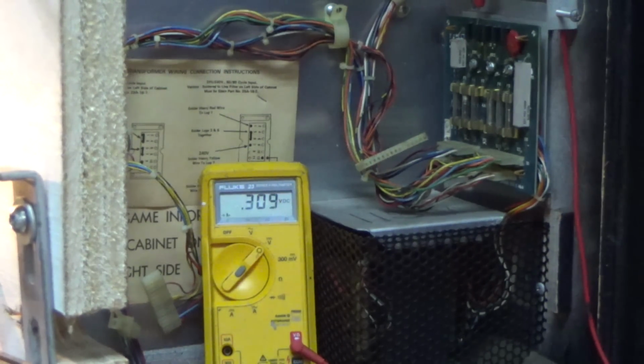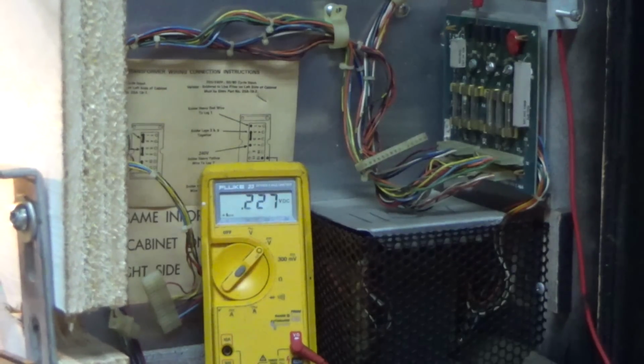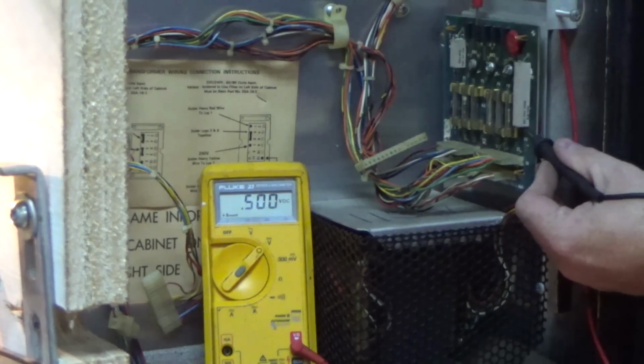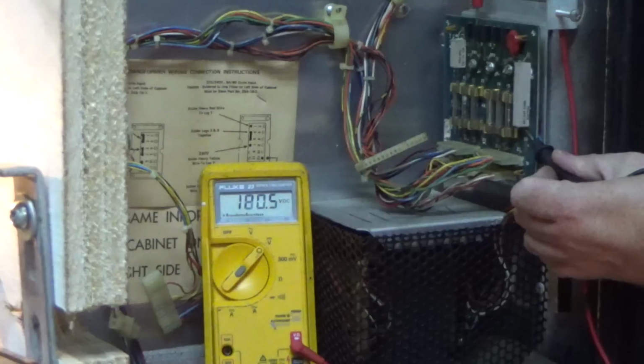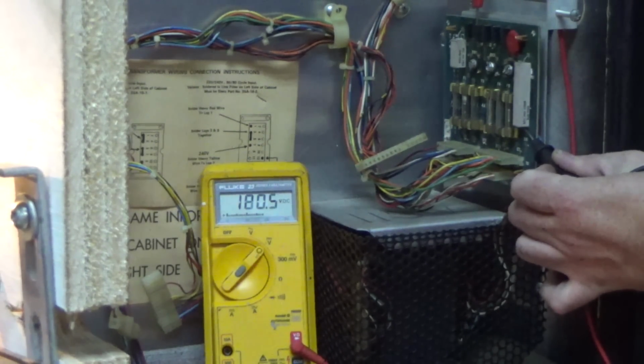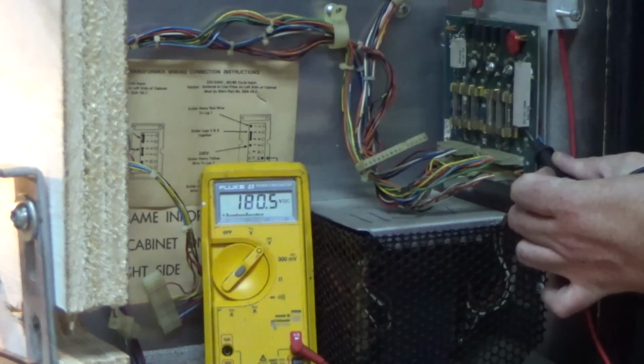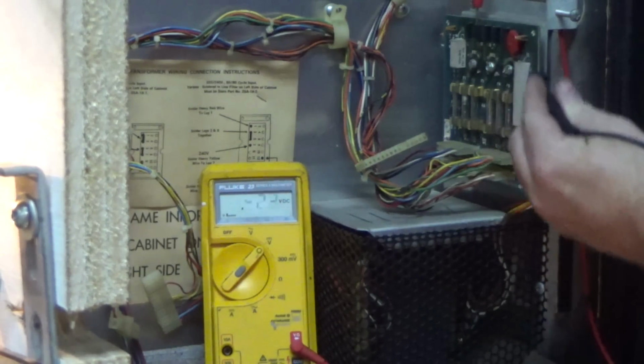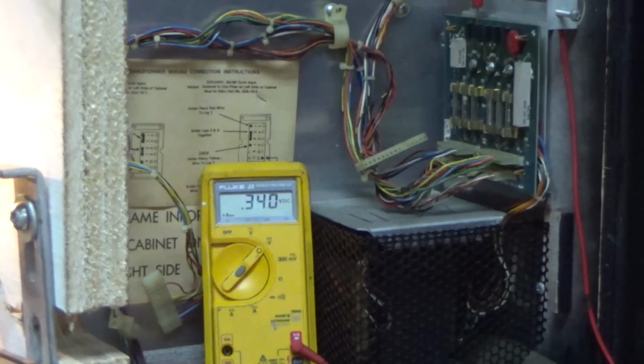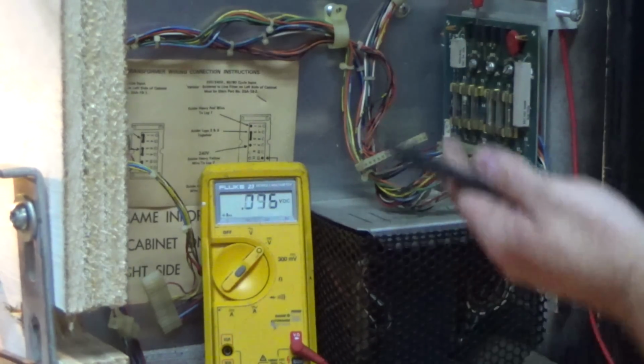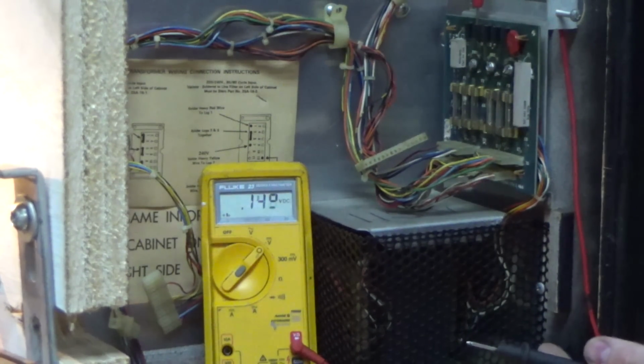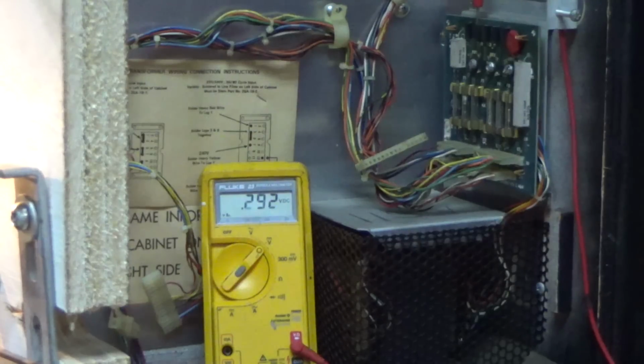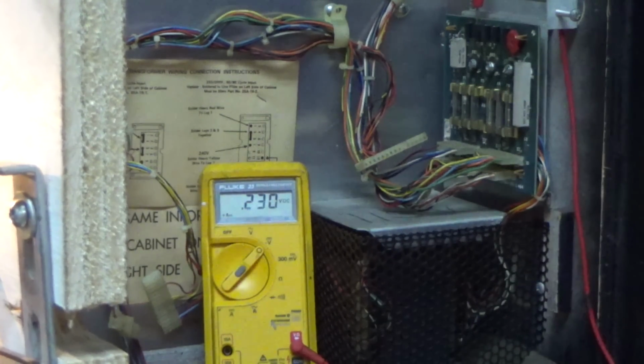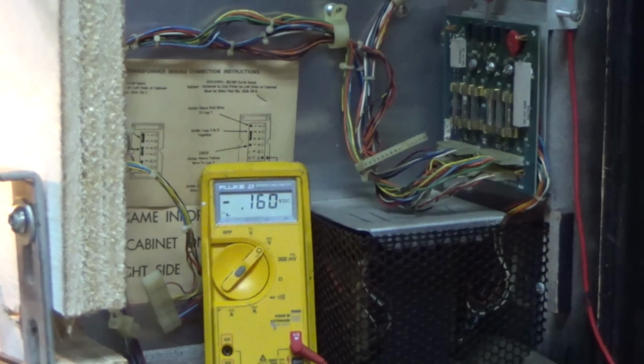Now I'm about to screw that all up with this one. Watch how off this one is going to be. So it's 180 volts, but it's supposed to be 230 volts. Now why is that? It's because there's no capacitor here to raise it up, it's just the way the thing's designed. When you plug in the solenoid driver board, there's a filter capacitor on there that raises the voltage up to like 230, and then they rectify it down to 190 originally, but we usually set it on 180. So that's actually correct as well.